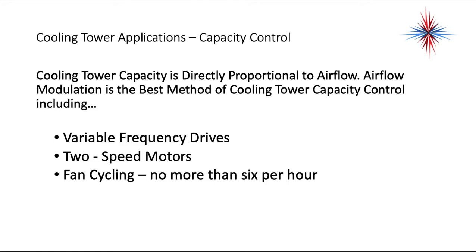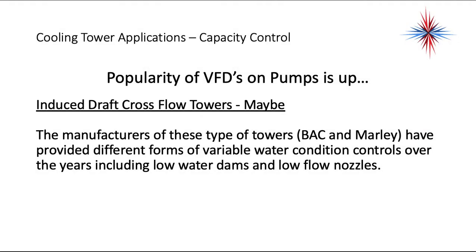The best method of cooling tower capacity control is on the air side, using variable frequency drives, two-speed motors, and fan cycling no more than six cycles per hour. We might have a temperature swing of the water in the tower, but we do not want to cycle the fans on and off more than six times per hour — the motors will eventually wear out.